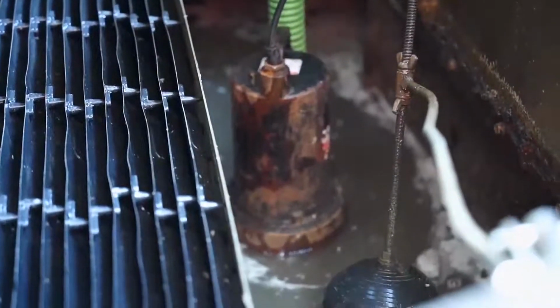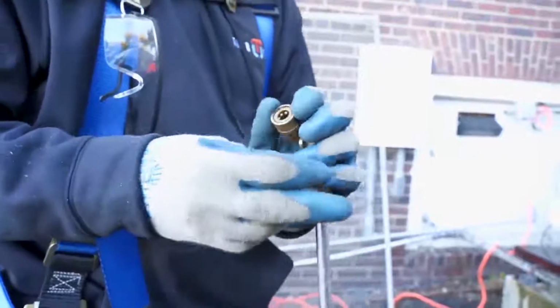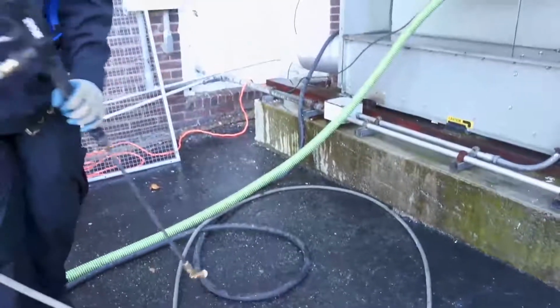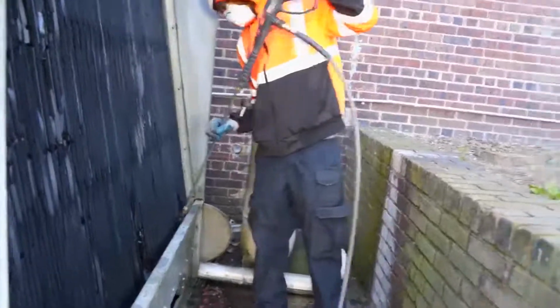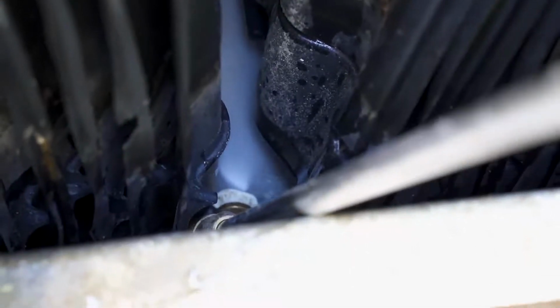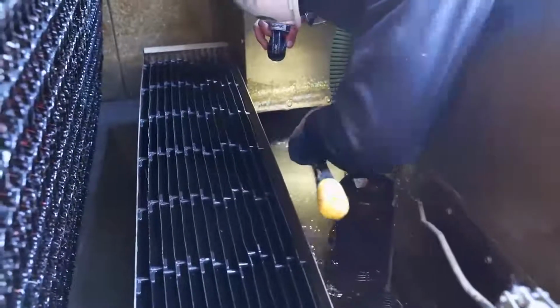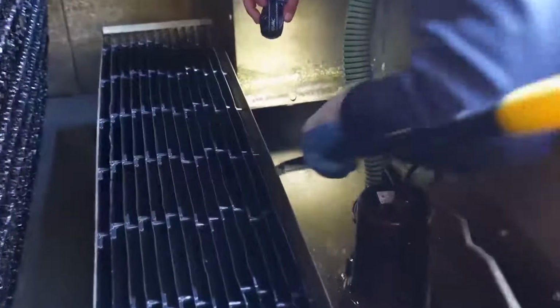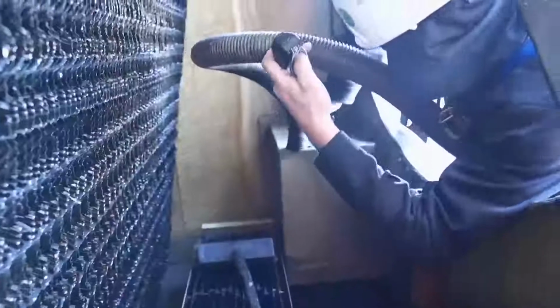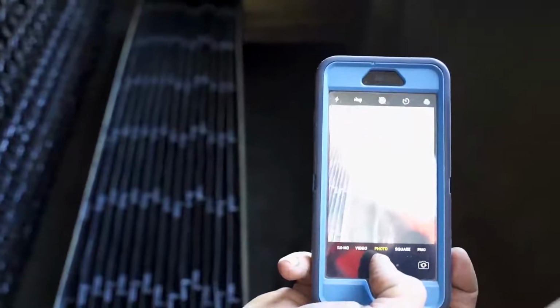Next, add the sump pump to the tower so that we can suck out the debris from the basin. To do this, put the sump pump in a low spot of the basin, or an area where all dirt accumulates, and double check that the pressure washer is set up correctly. Turn on the makeup water, drain, and begin pushing the debris from the outside basin to the inside, while your partner directs debris to the sump pump. Notice the protective mask keeping water droplets out of your lungs. Use the vacuum to get the areas the sump pump won't reach and pick up the heavy metal flakes and debris. Take photos of your successful cleaning at the same position as the before photos.